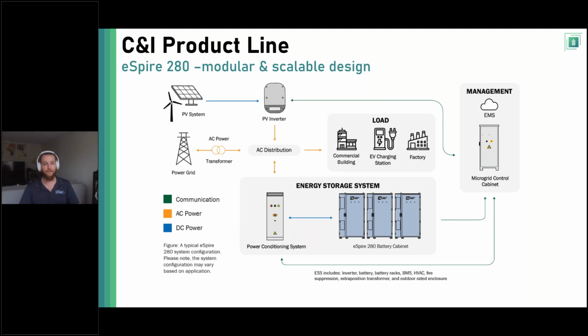But you can see the PV inverter up top. That's not in our scope, but like I said, that green line connecting to the microgrid controller, that's what we're helping you select the equipment for. We know that that green line is going to be uninterrupted. We can send and receive Modbus signals from the PV inverter to our controller and vice versa, right? So for example, say we're in a fully off-grid system, and the battery is fully charged, and there's not enough load to offset the power being output from the PV inverter. We'll send a signal to the PV inverter to curtail the solar if need be, right? They're just some of the functions that can happen via that Modbus. But like I said, I'll send out a more technical line diagram. This is just how we are AC coupling this eSpire 280 system.